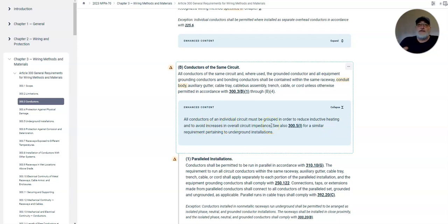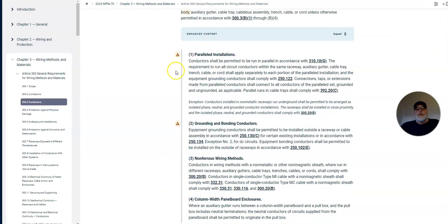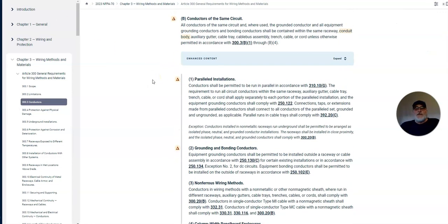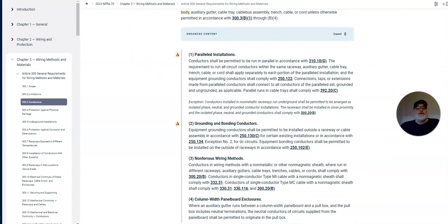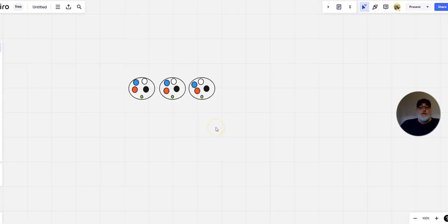Whenever you start separating these conductors, the harmonic balances get thrown off, and it just starts causing havoc in the electrical system. Now we're going to look at these conductors in parallel and give you an idea. I want you to look at this. This is a really rudimentary drawing, but it's an example of three conduits with three hots, black, red, blue, a neutral, which is white, and your ground.